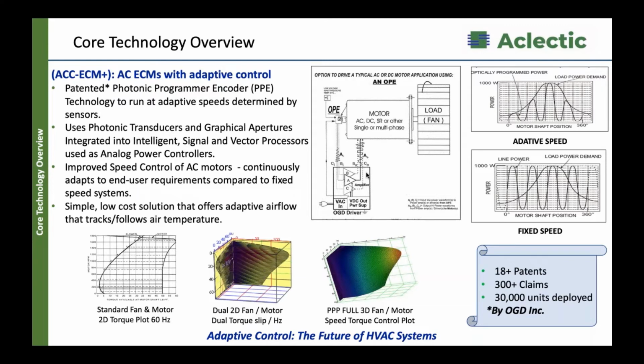You had mentioned some yesterday—there were a couple of good questions about the ECM and the size of the unit, the electricity. So whether it's a 50 hertz or 60 hertz motor, whether it's a 20th horsepower or a 2-horsepower motor, the same box can be programmed to operate all of the above. Often one program will still work across that range of units without major modifications. So all we're showing here is that the technology not only enhances external system performance, making the system run smarter, but also makes the motor itself run smarter. If a motor is running a fan versus a compressor versus a pump or an electric heater or a light bulb.